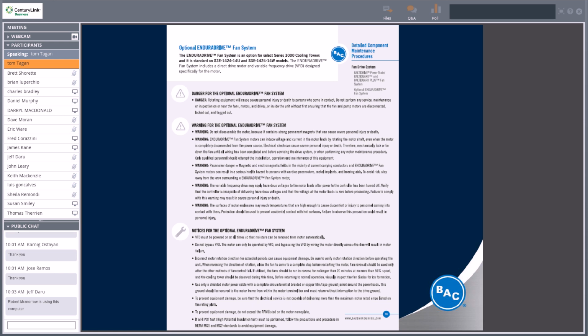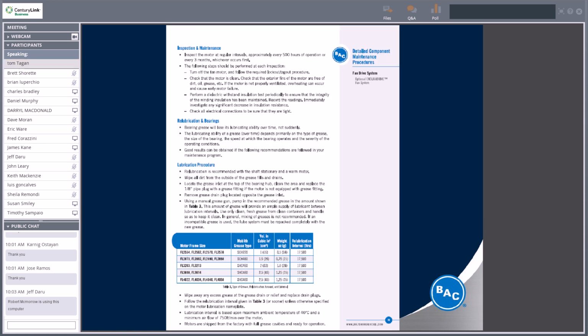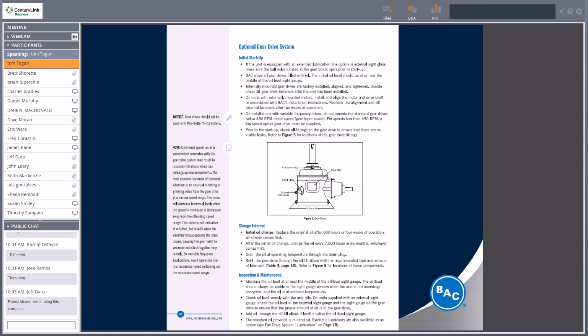So that's an option to think about. If there is justice in the world, you guys would have some influence on the design of all your new facilities. So that's just something to think about, the direct drive motor. A little bit of propaganda, but it is just a third option on how to turn that fan. Again, it gives you all the specific lubrication procedures on the bearings, on the fan motors, and it talks about maintaining that particular type of drive system.